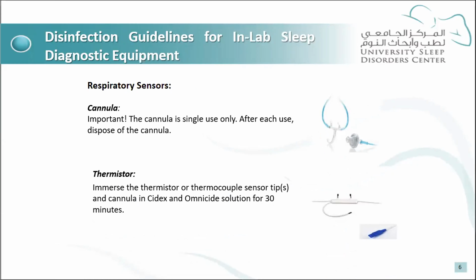Next one is the thermistor. And as you are all aware, the thermistor is one of the most important parts of the device that can be affected by COVID-19. And how to disinfect the thermistor: you need to immerse the thermistor or the thermocouple sensor itself in Cidex or Omnicide solution. This has to be for at least 30 minutes. And it's very important to make sure that it is dry before you use it for the next patient.